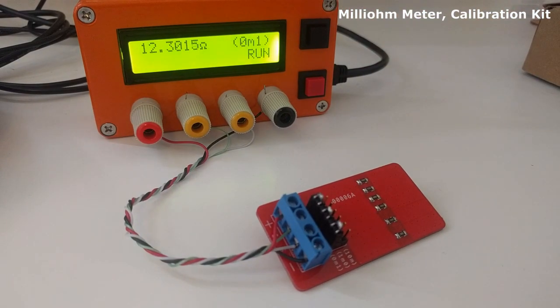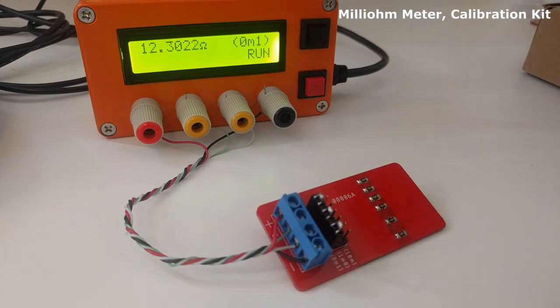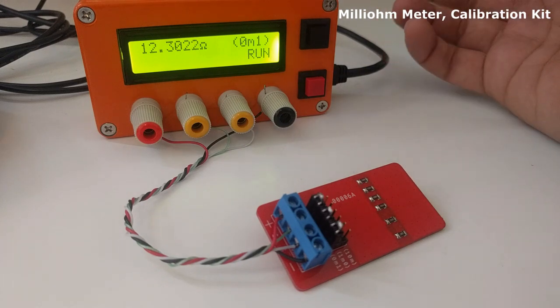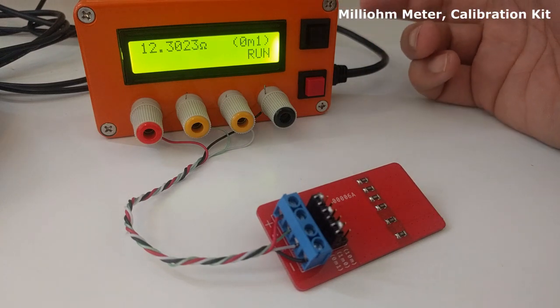In this scale, as the current is bigger than the current in the others, the resistance increases with time. This is because of the temperature increment in the calibration resistor and inside the meter.